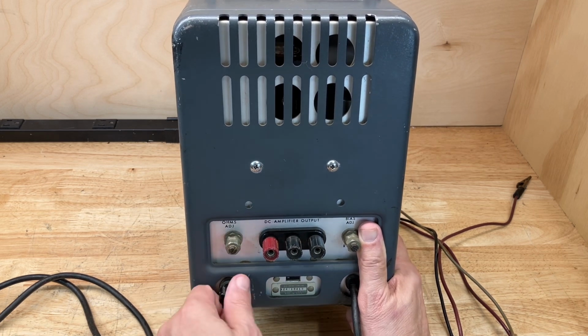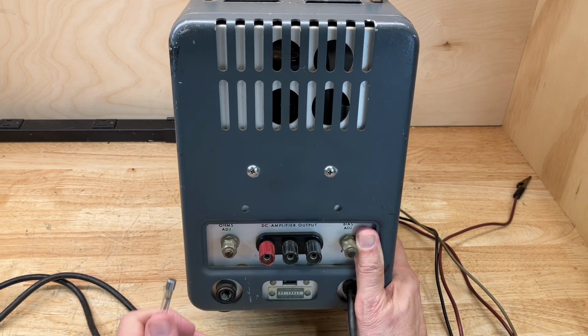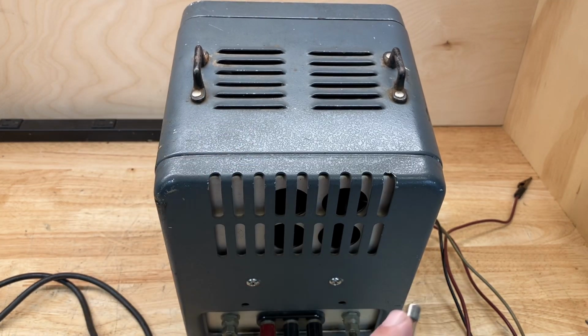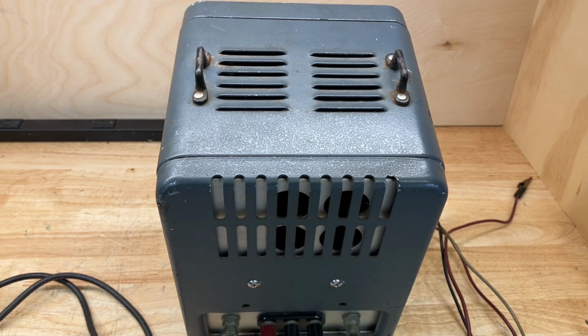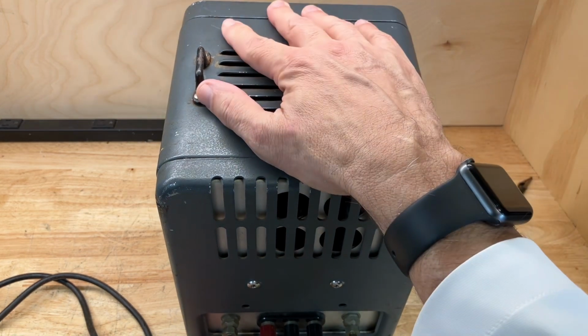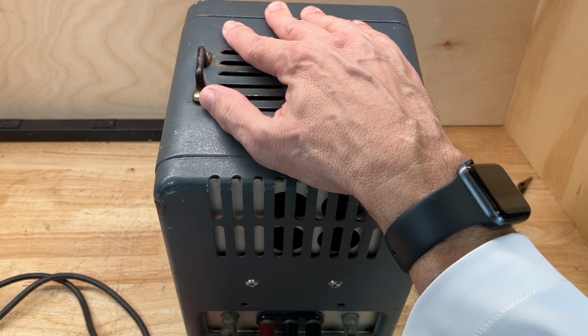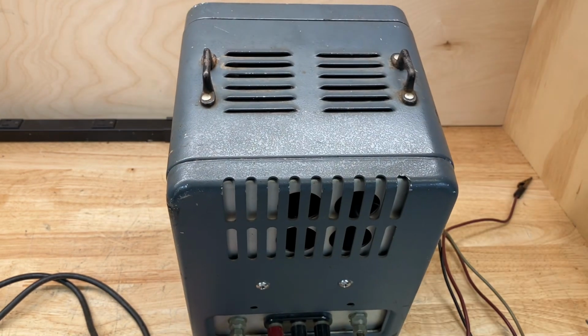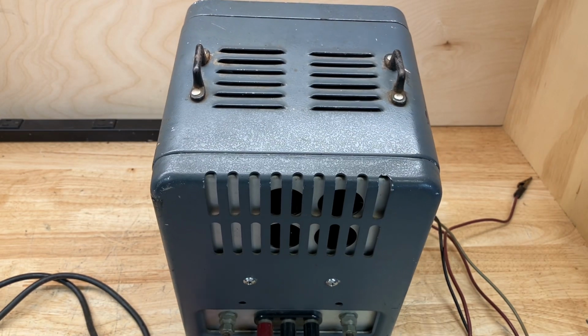I also like to check the fuse. I know in this instrument it's supposed to be a half amp slow blow fuse. Let me see what it says. Doesn't look like a half amp. This is a 3 amp slow blow fuse. That is not the correct fuse. There's no way this instrument's going to draw 3 amps of current, not even close.